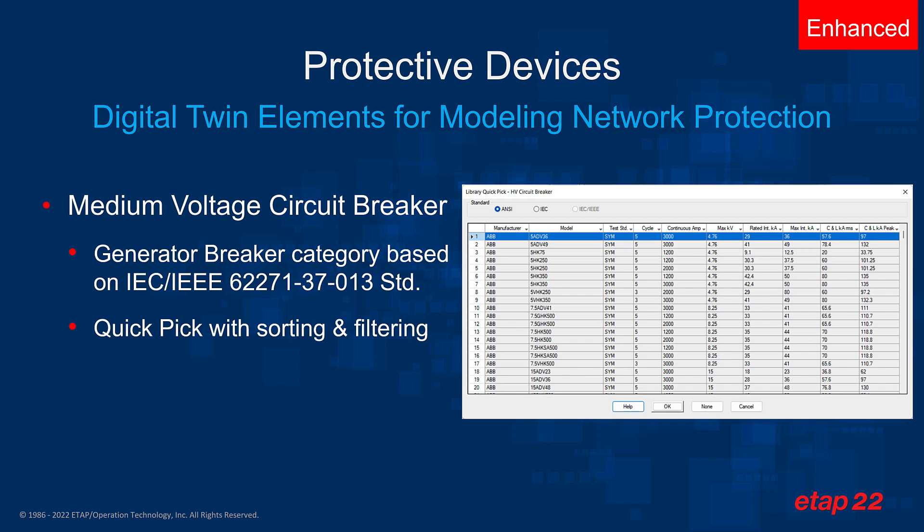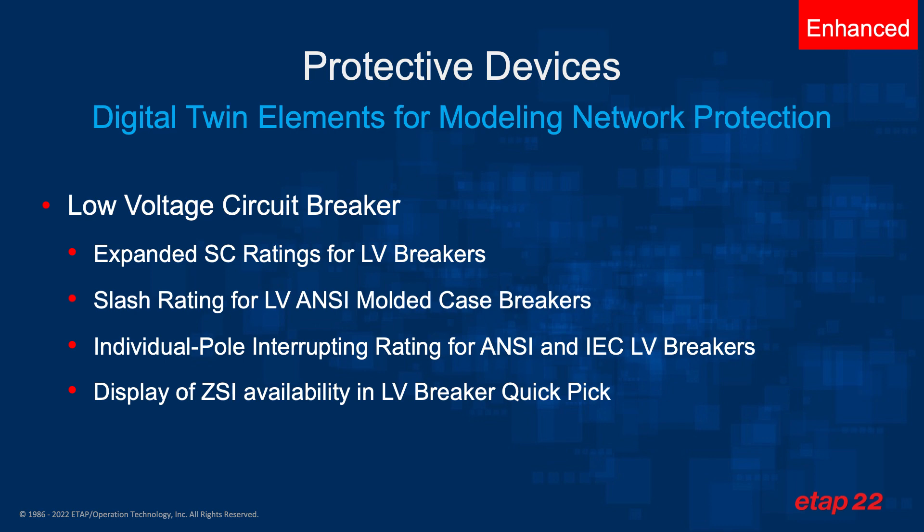its size or rating very quickly and efficiently. There are similar standard improvements also for low voltage circuit breakers. We've not only expanded the short circuit ratings for the low voltage breakers, but we've done so by adding the slash rating for LV ANSI molded case breakers and individual pole interrupting rating for ANSI and IEC low voltage breakers.